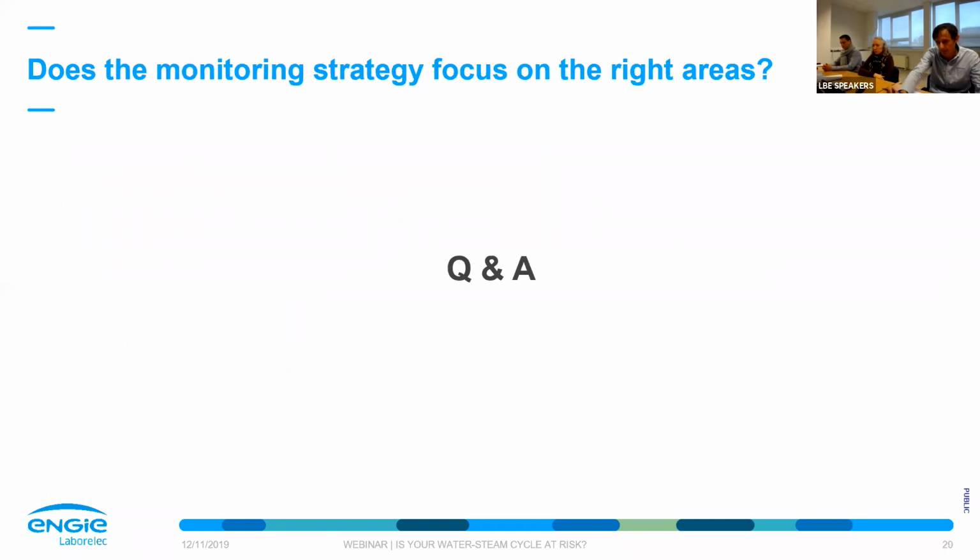All right, if there are questions, feel free to ask. Yes, thank you very much, Alex. We have two questions currently from the audience. The first one is: to increase pH in the HP drum, which is better, caustic dosing or TSP? We follow AVT as of now.